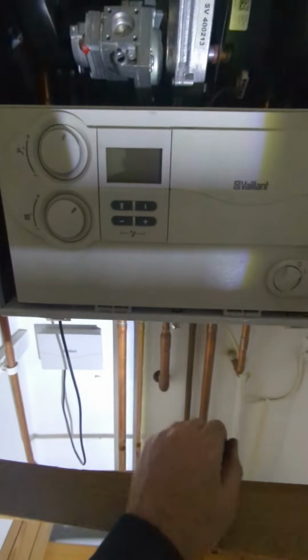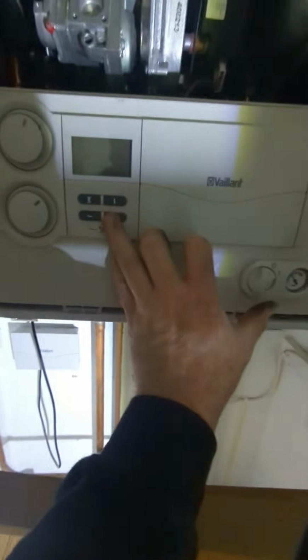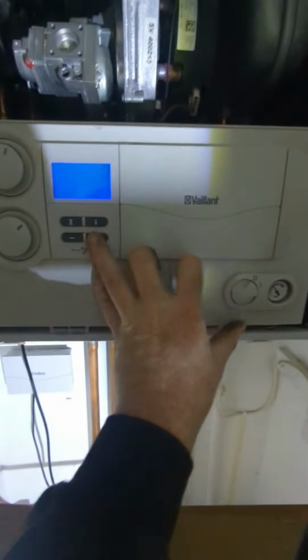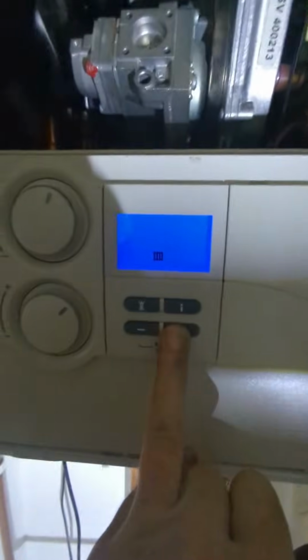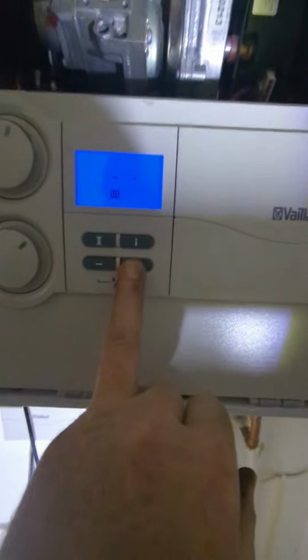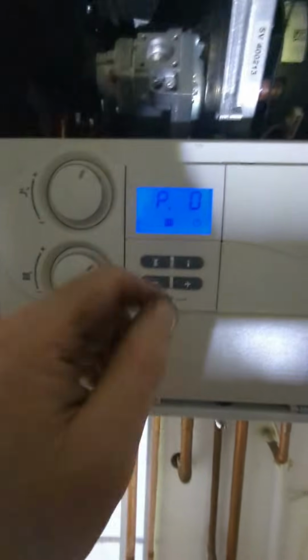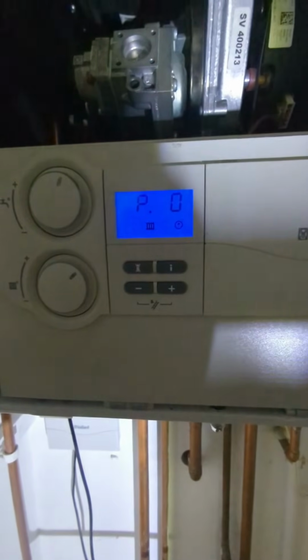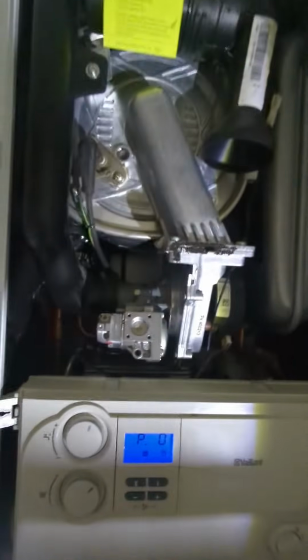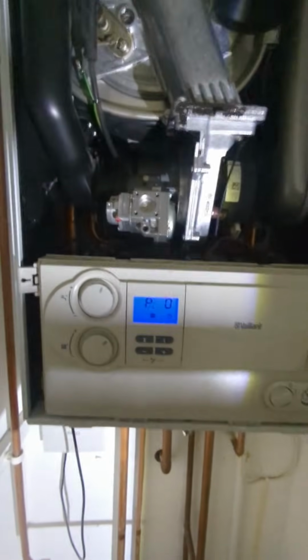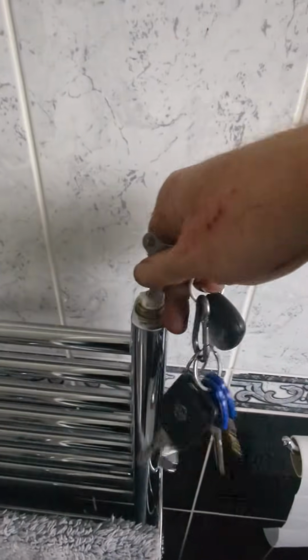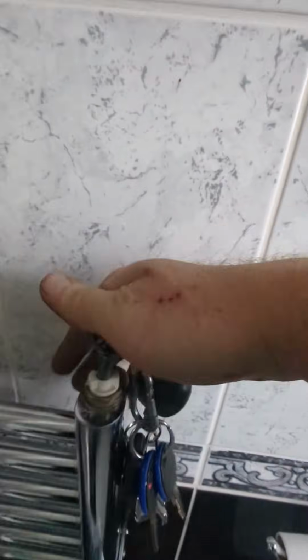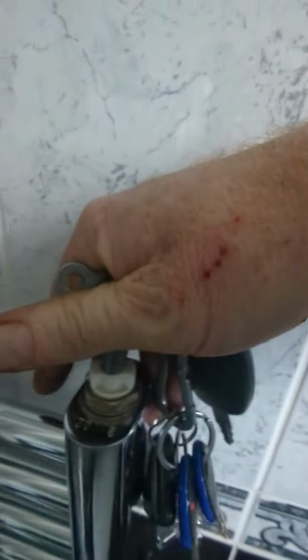With the Vaillant boilers, we can do an air purge, which is very handy for after working. So we go into the purge, you're just turning it on whilst holding plus. And then there's our P0, which will vent any air out of the system, because we've drained the boiler. It's important we do this. Then also go around and give the rads a good bleed.